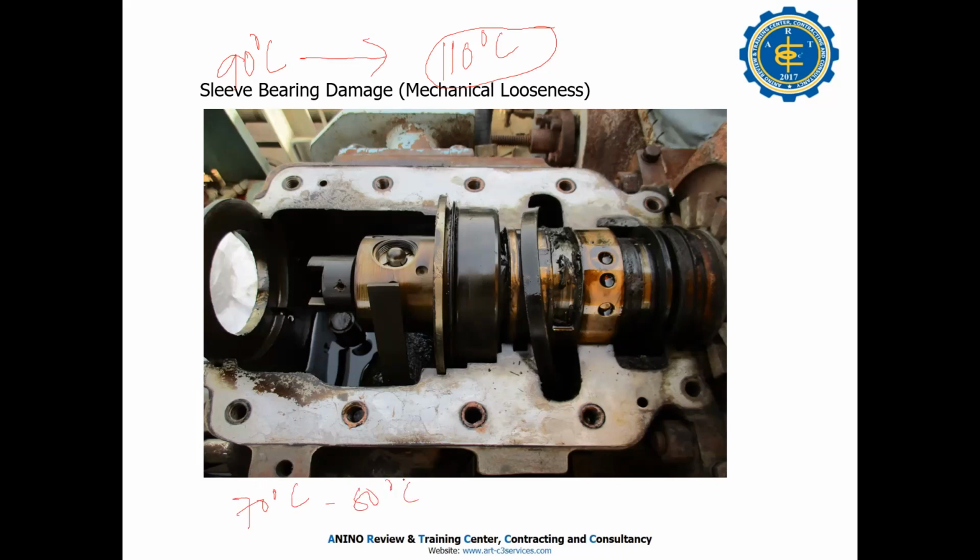How much is it on your side now? Maybe lower? Your bearing housing temperature is lower. Yeah, okay. If it is 60, it's good.